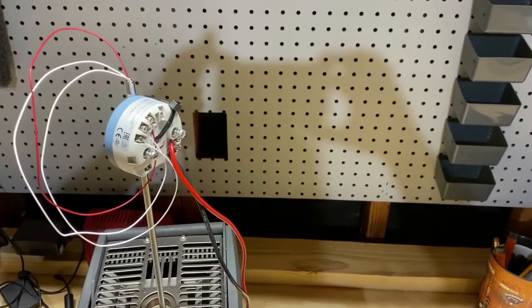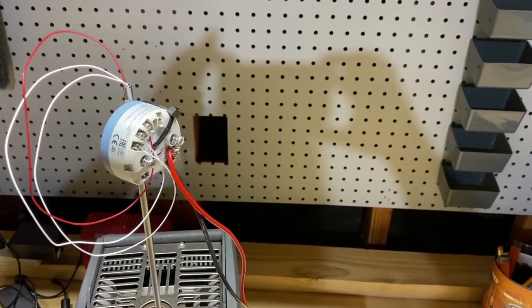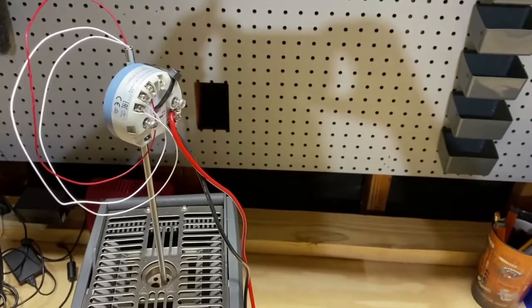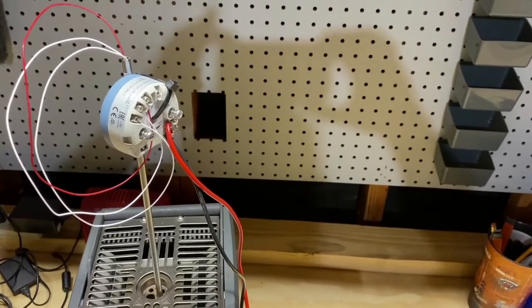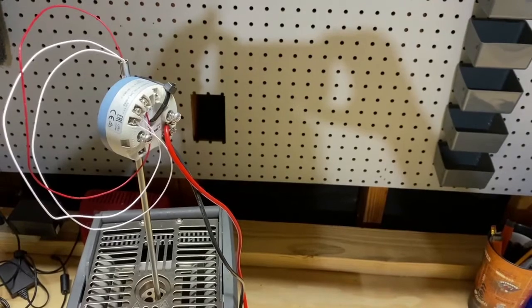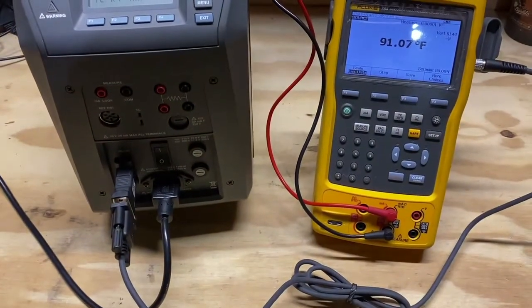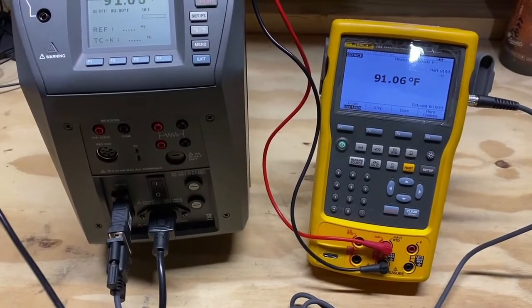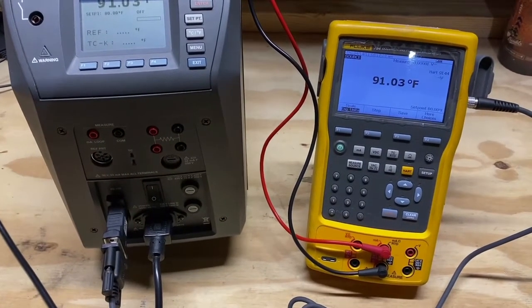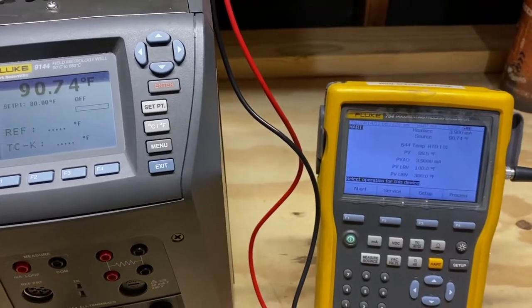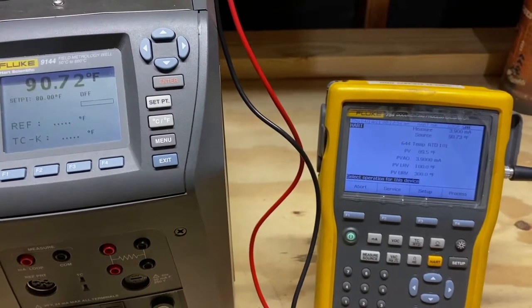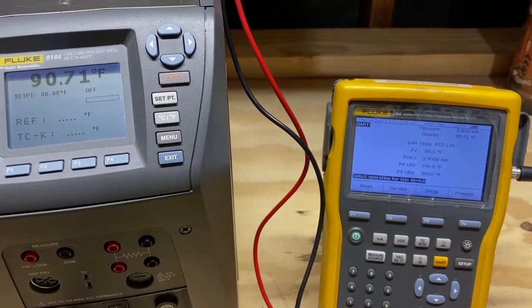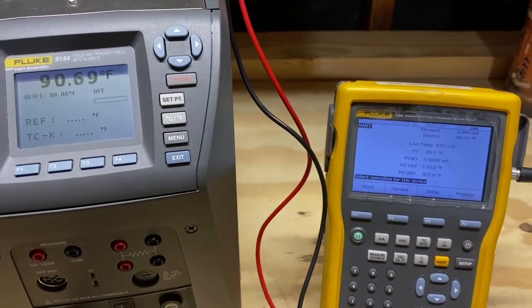To conduct a demo calibration, we have inserted a 3-wire RTD into the dry block that is connected to an Emerson 644 transmitter. The transmitter is being powered and measured simultaneously with the 754 while also being interfaced using the HART protocol. Having connected the 754 to the temperature transmitter, we can see that the basic HART information is now displayed on the screen of the calibrator.